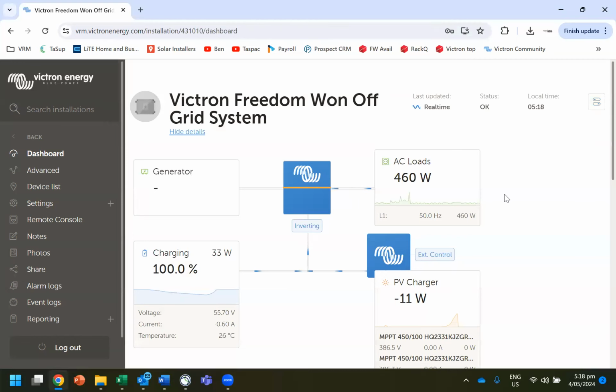Now you can turn the inverter charger settings off and on so that you can see settings here, but there's a danger in that. The danger is that you can accidentally turn the inverter off, which means you've just killed power to the site. What happens when you kill power to the site? You lose internet. You cannot then fix your accident by turning the inverter back on again. So unless you're an advanced user and you don't want to risk this sort of thing, leave those settings off.